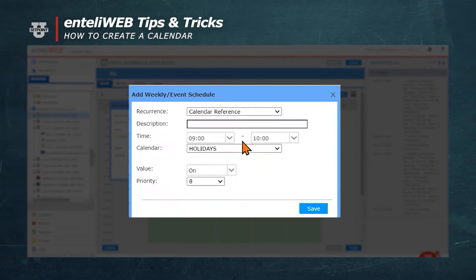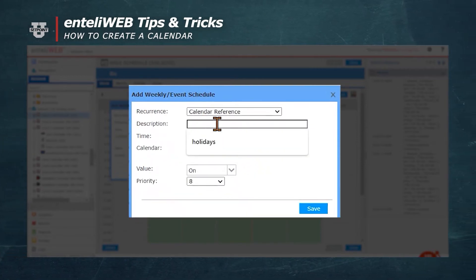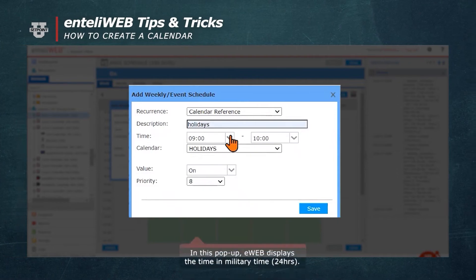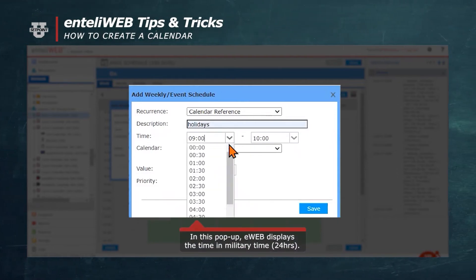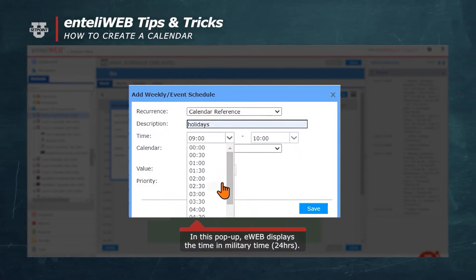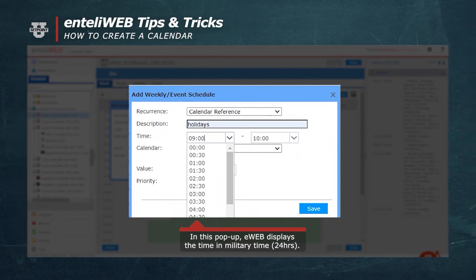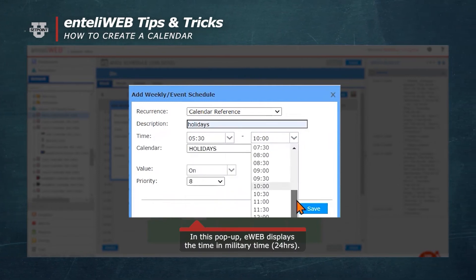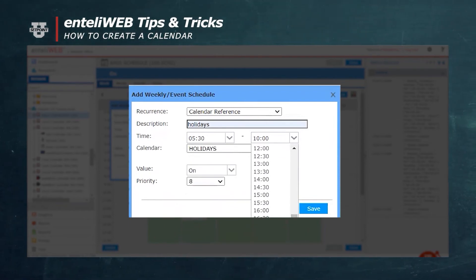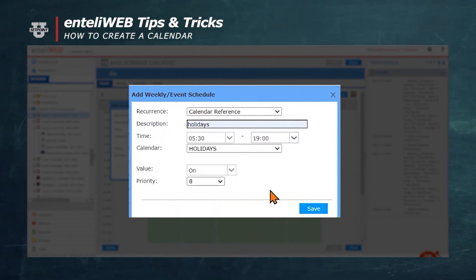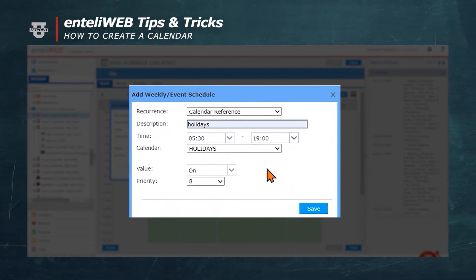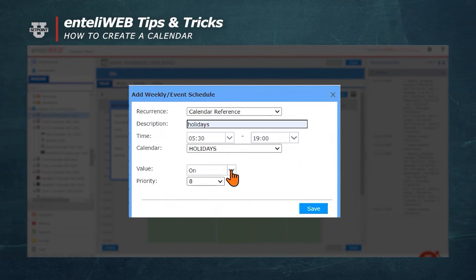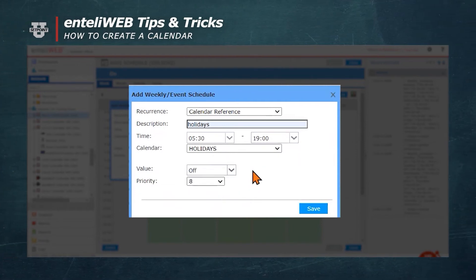As you can see, we'll put another description in here. We want our time to be outside the normal runtime. If normal runtime starts at 6 in the morning, we would want this to start at 5:30. If our end time is normally 6:30, we would want this to end at 7 o'clock. The calendar is titled Holidays, and the value is now going to be off instead of on — we want the equipment to be off during this time period.